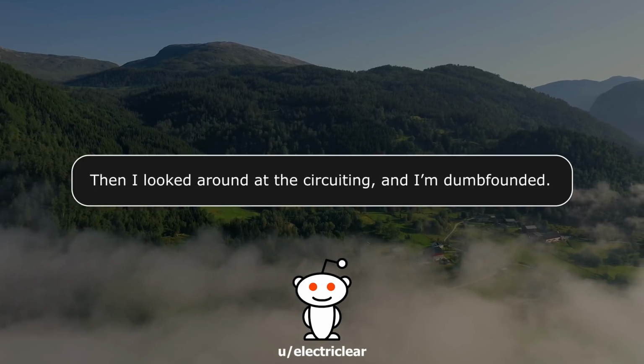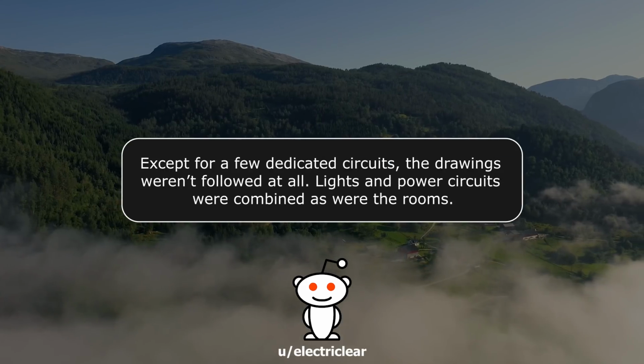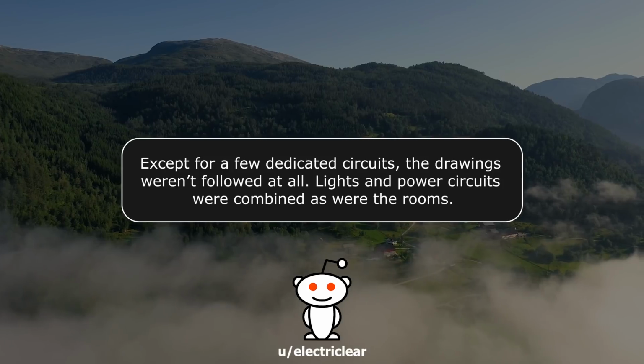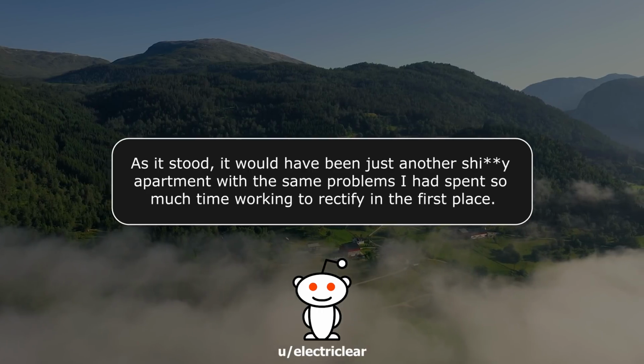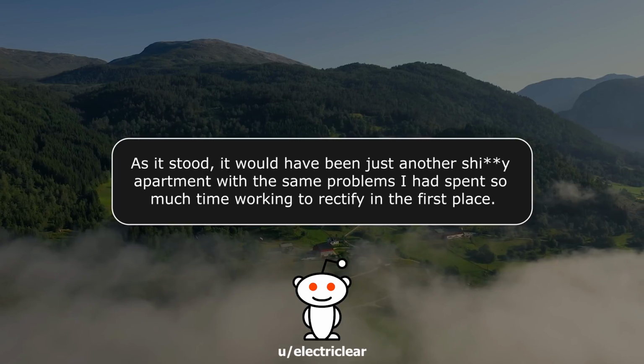Then I looked around at the circuiting, and I'm dumbfounded. Except for a few dedicated circuits, the drawings weren't followed at all. Lights and power circuits were combined, as were the rooms. As it stood, it would have been just another crappy apartment with the same problems I had spent so much time working to rectify in the first place.